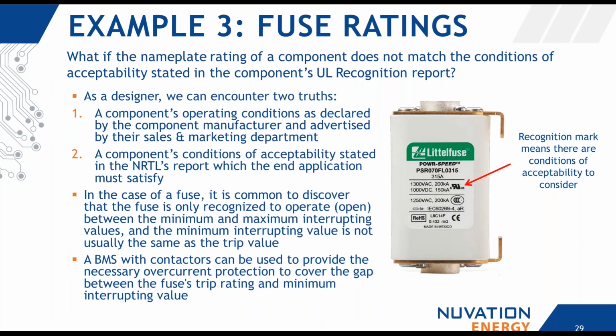But there's also the conditions of acceptability, which are stated in an NRTL's report, and the end application that you're using the component in has to satisfy those conditions. So for example, an RU mark on a fuse means that there are conditions of acceptability to consider. You get the report and look at what those conditions are. In the case of a fuse, it's common, and not unique to any one fuse manufacturer, that it's only recognized to open between a minimum and maximum interrupting value. And the minimum interrupting value is not usually the same as the trip value.